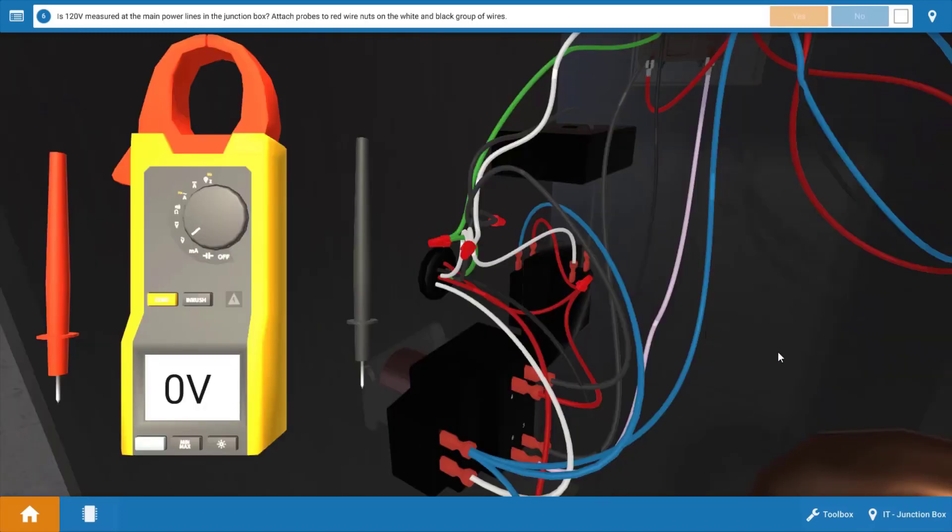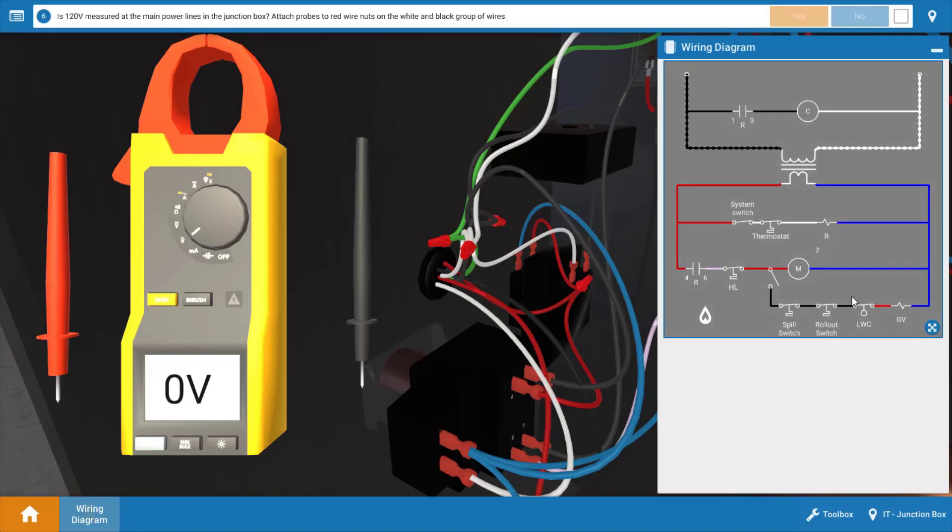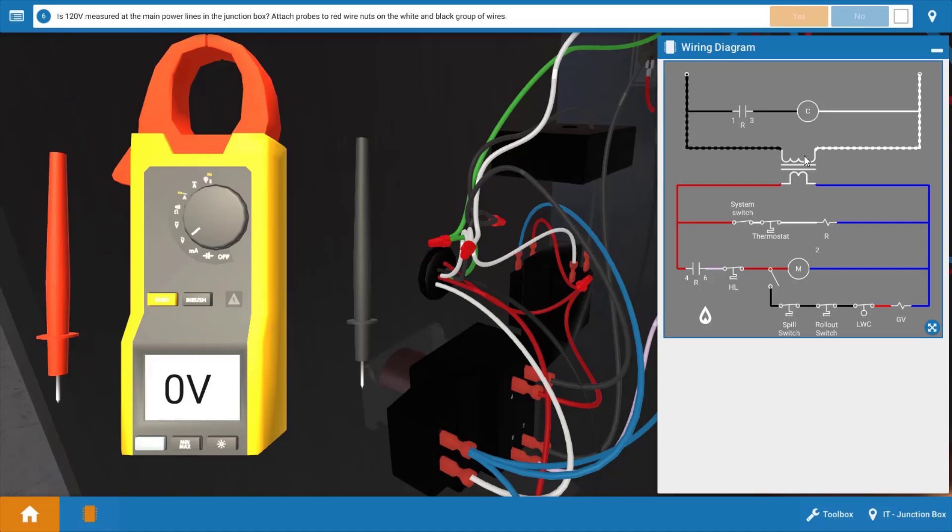So now that we verify we don't have 24 volts out of the transformer I just want to show you something on the wiring diagram. If you click on the wiring diagram we can see that here's the transformer and we had previously measured at the hot and neutral connections coming in. So that verified 120 volts to the primary of the transformer but we don't have secondary voltage. So again this verifies that the transformer is faulty.